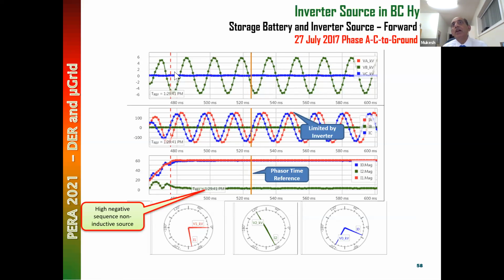You see, the A to C ground fault happens to be very close to the relay. The voltage A to C collapsed, and this is the B phase voltage. Actually, B phase voltage also depressed quite a bit due to high current. And look, the current in the other two phases was limited by the inverter to, I think, 2 per unit. In this specific inverter, the current is limited to 2 per unit. But anyway, it limited the current. It did not go too high, but limited current to 2 per unit.